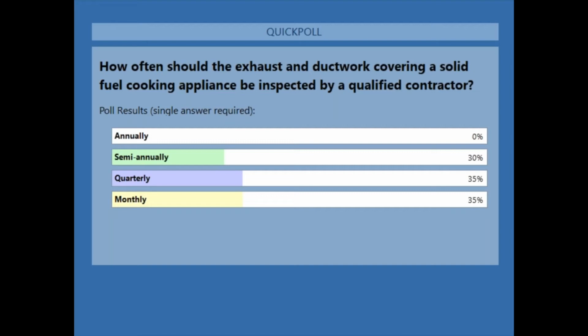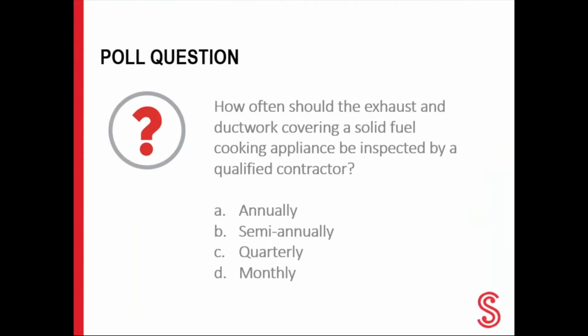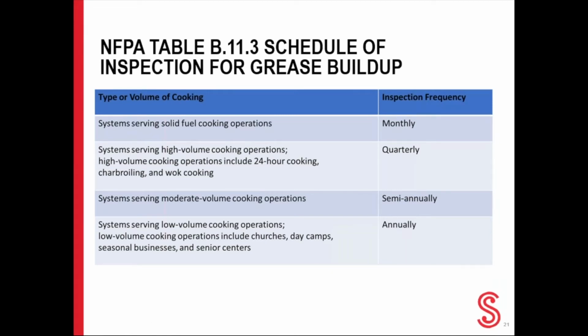The exhaust and ductwork covering the solid fuel cooking appliance should be inspected monthly by a qualified contractor. If the inspection reveals a buildup of creosote and/or grease, then the contractor should continue with cleaning the hood ductwork or piping. And on the next slide here, you'll see a chart from NFPA that kind of goes over that. So it breaks down the requirements based on your cooking apparatus. NFPA, this is out of NFPA 96.